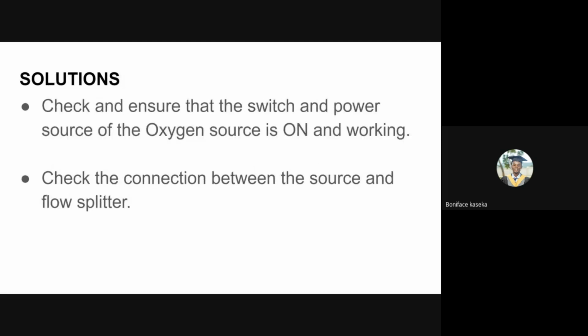On the next slide, I'm going to talk about the possible solutions that you can use to tackle such a problem. First and foremost, you need to make sure that the oxygen source you are using is switched on. In terms of an oxygen concentrator, make sure that it is switched on and in good working condition, because if it's not, there's no way you are going to be delivering oxygen into the oxygen flow splitter. So make sure that it is on, and you can also check the mains to see if there's power.